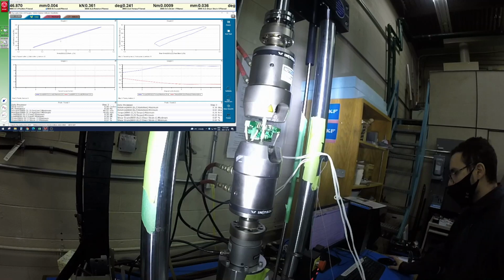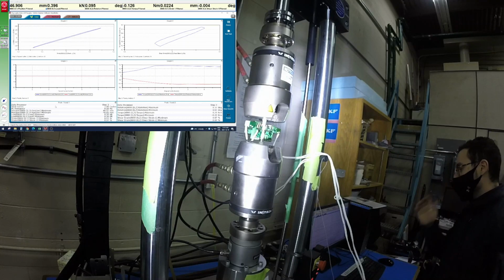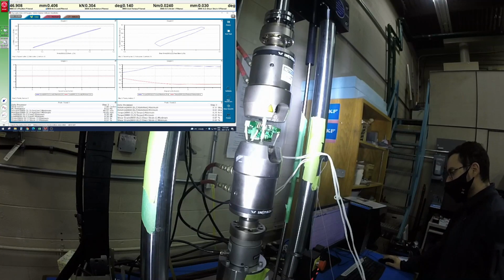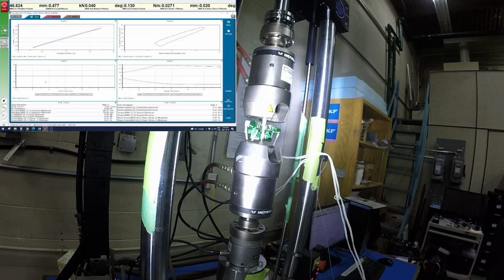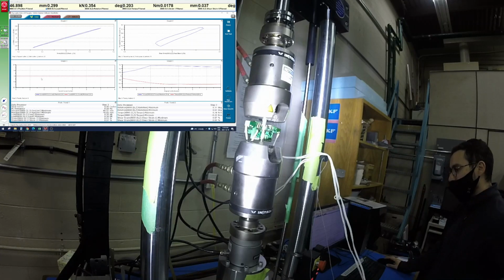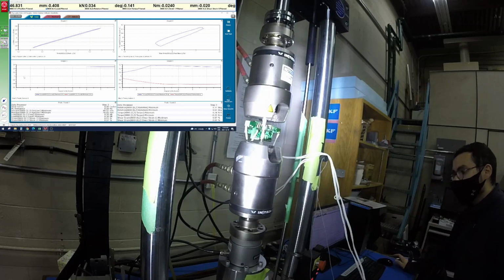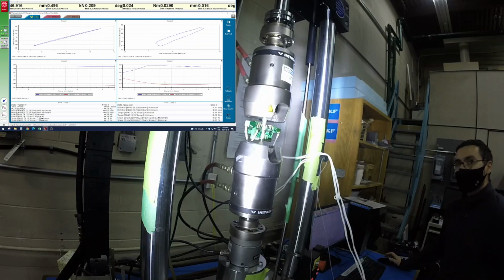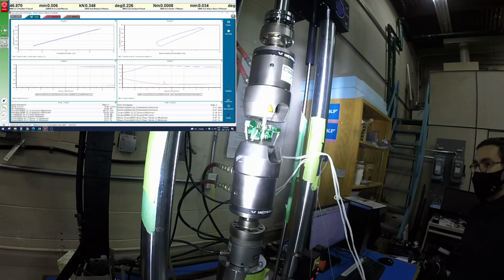The other things that are showing the live data are all on the top of the screen here. All of the max mins and the setup test parameters are on the bottom. So we've accumulated 7 cycles here. You can see our axial forces were perfect really from the first cycle here on the left. That's hitting the peak and valley targets quite easily. We can rescale this by right clicking and then clicking auto scale.